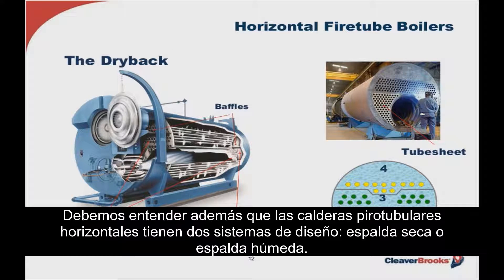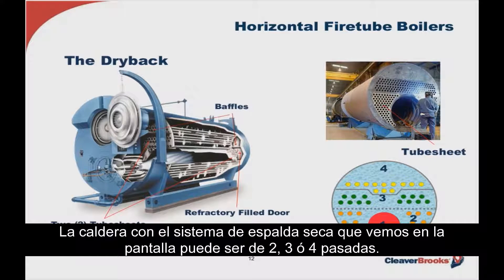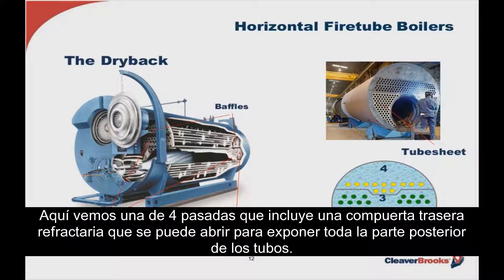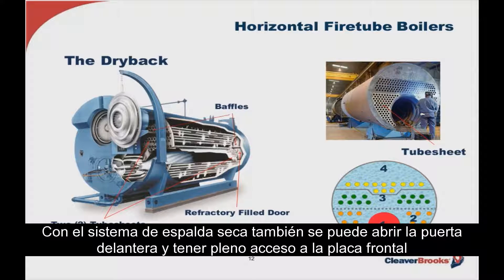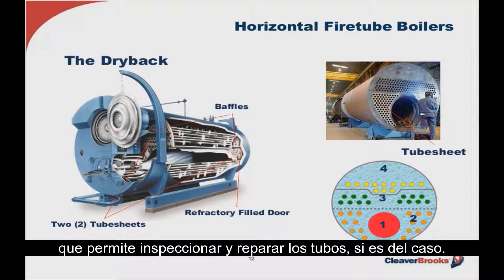The horizontal fire tube boiler comes with either a dry back or wet back design. The dry back fire tube can be either a two-pass, three-pass, or four-pass design. It includes a refractory-filled rear door which can be opened to expose the entire rear tube sheet and the tubes affixed therein. In a fire tube boiler, the flame and hot gases are contained within the tubes and the water surrounds them. You can also swing the front door for full access to the front tube sheet — all for inspection and tube and furnace repair if necessary.